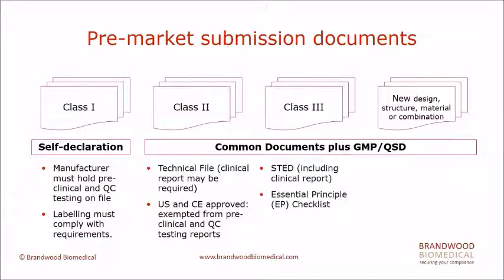For Class 3 devices, apart from the common documents and the QSD application, QSD certificate, the full technical file in an STED format is required, including the clinical evidence report and the essential principle checklist. For novel devices, the full technical file, including the clinical evidence report, is required. So the message here is the higher the classification, the more documents will be required as part of the initial applications.